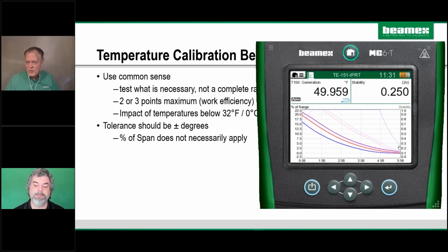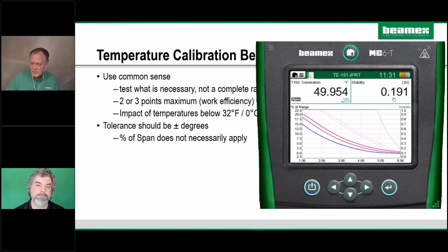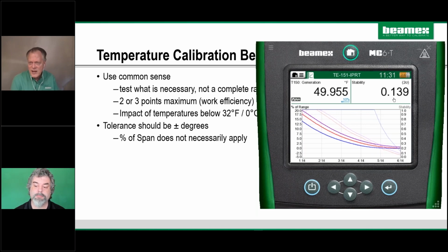But this stability is really cool to me, because when you see all the sensors, right now they're below 0.2, you're pretty close. And when it gets down to 0.1, we're talking 1/10 of a degree stability with a 95% confidence level. It just gives you a lot more confidence in the measurements you're making with this type of technology.